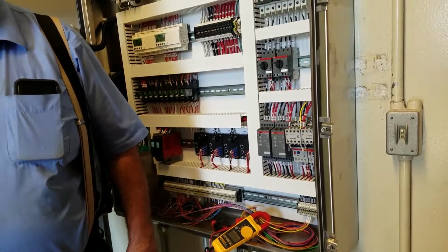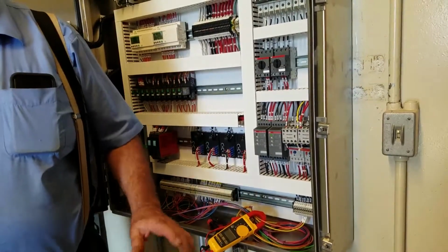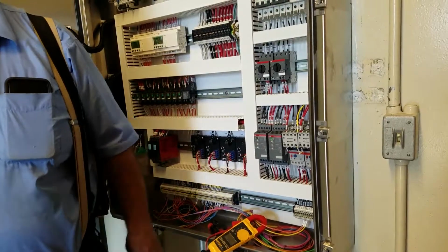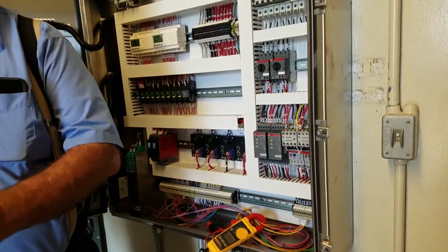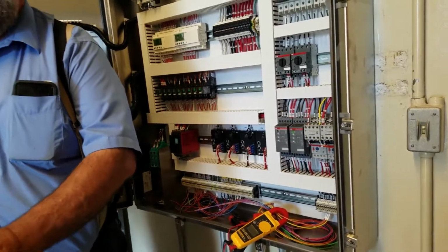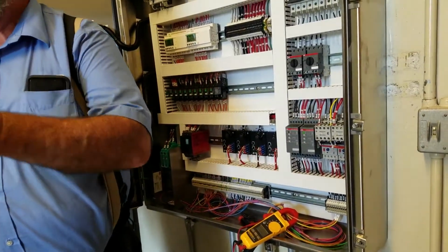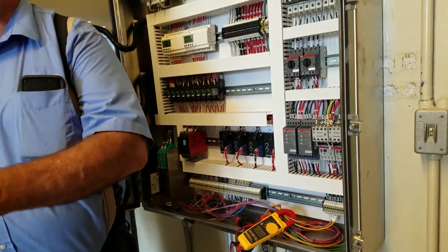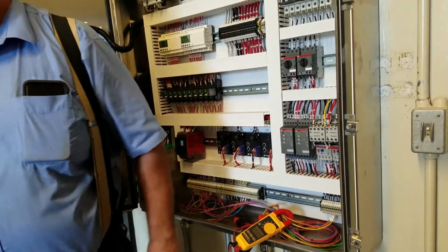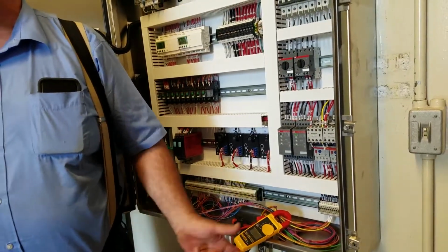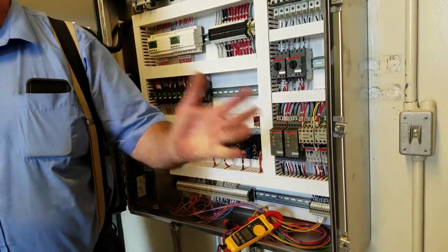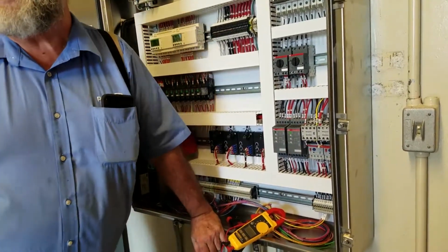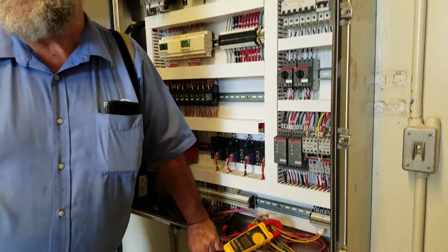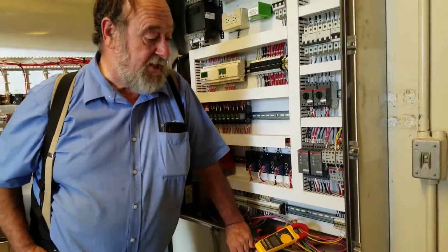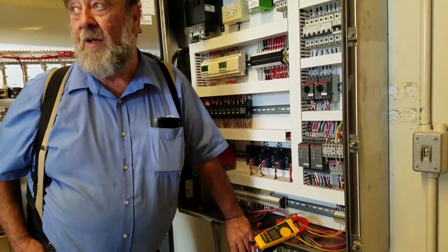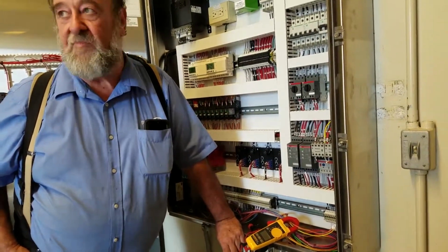I had this job where they had all kinds of problems with their press, tripping out all the time, giving fits, and they didn't tell the electrical contractor to change the PVC pipe to rigid pipe inside concrete above ground. So he did the transition above ground in open air. Every one of those connections cracked. So they had rain, they had snow, we all had a lot of rain, and the conduits filled up with water. Caused some problems. But water in conduits is a big issue. It does happen. Megger tester's a great investment. We've got a lot of that going on at this plant. And water in conduit outside.